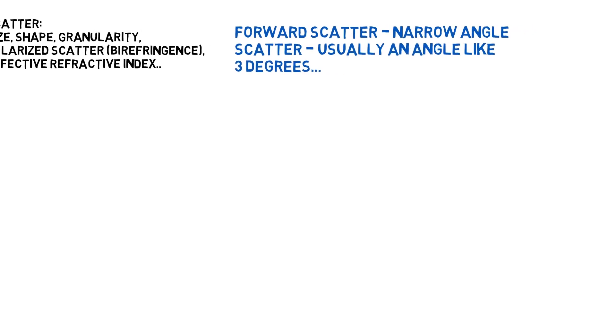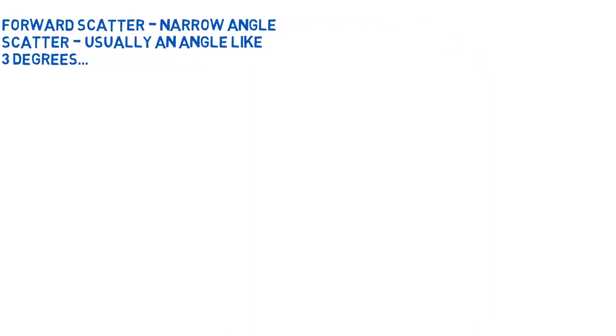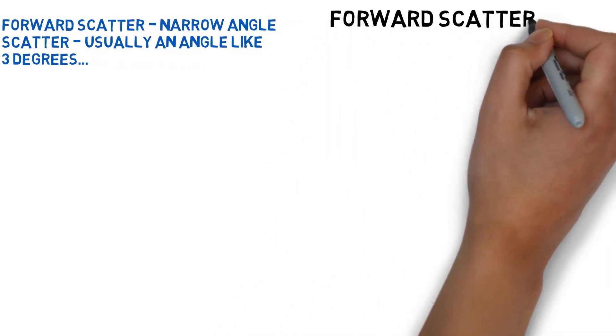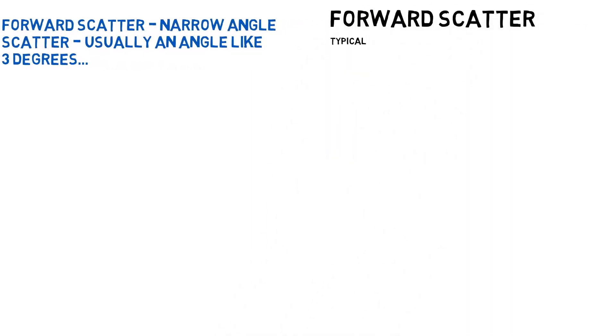First, let's talk about forward angle scatter, which is also called narrow angle or FALS, F-A-L-S. We mostly collect this at about 3 degrees angle off the laser beam. FALS signal strength is very large — it can be 100,000 to 1 million times the intensity of the fluorescence signal.